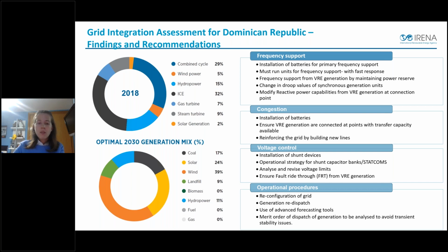58-62 Hz, ensure reactive power capabilities are 0.85-0.9 leading lagging power factor at connection point, ensure VRE generators are connected at points of the grid where delivery of additional generation is feasible, and ensure fault ride-through capability of variable renewable generation, guaranteeing non-disconnection at voltage sags of 0 per unit at the connection point for a duration of 150 to 100 milliseconds, and reactive current contribution that ensures supply in the system. So with these results and recommendations, I'm just finishing my presentation for today.